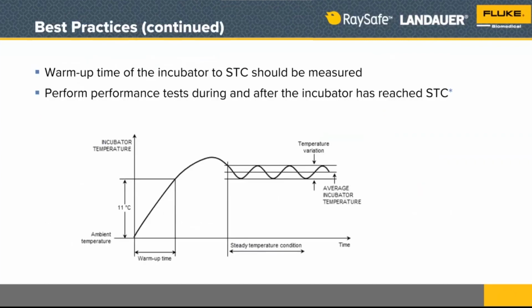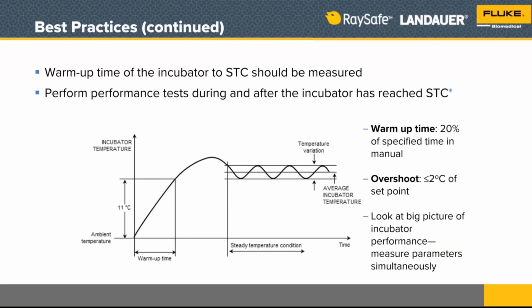All right, and we're back to what are we measuring about temperature? Again, like we did before, the warm-up time and the overshoot. And we're looking at the big picture of incubator performance, making sure that the control band for our temperature is kept, that we don't have a thermal runaway of our temperature control. It stays steady and controls that temperature within the band.